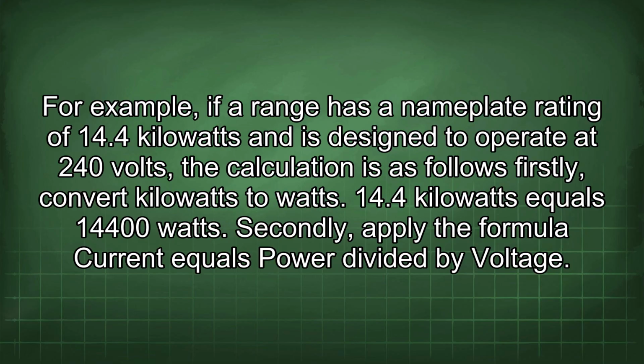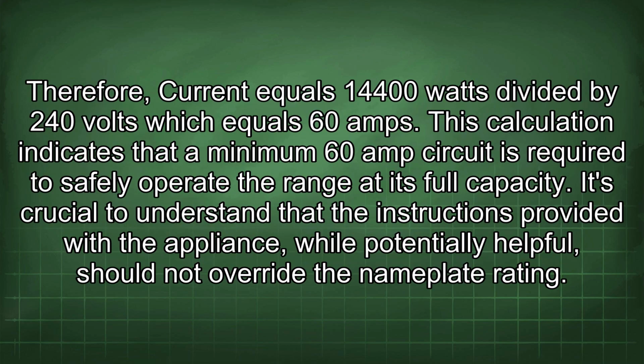Secondly, apply the formula current equals power divided by voltage. Therefore, current equals 14,400 watts divided by 240 volts, which equals 60 amps. This calculation indicates that a minimum 60 amp circuit is required to safely operate the range at its full capacity.